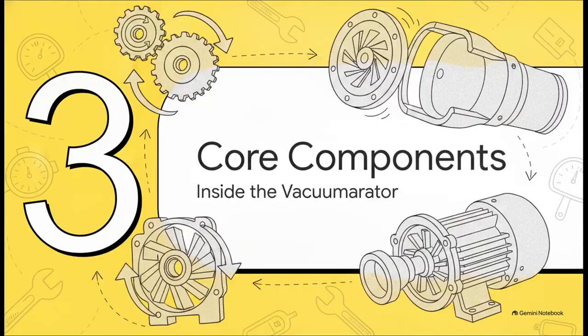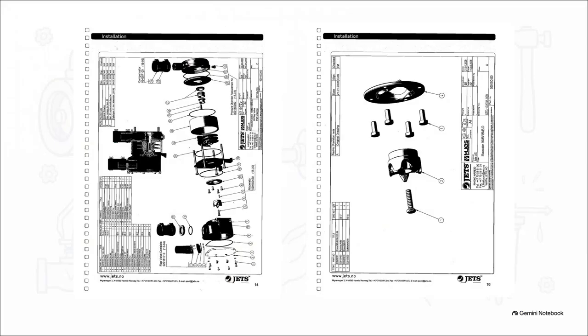the pressure side. All right, Section 3, Core Components. Inside the vacuumator. What's really cool to see here is the big macro picture right next to the tiny micro details. On one side, you've got the whole pressure chamber layout. You can see the layers, the pressure chamber itself, the O-rings, the end plate, and those big staples holding the whole thing together. But then on the other side, we zoom in on where the magic happens, the macerator. You can clearly see the rotating knife assembly that fixes to the shaft and how it works in total sync with the stationary knife to grind down the sewage before it even has a chance to enter the pump body.